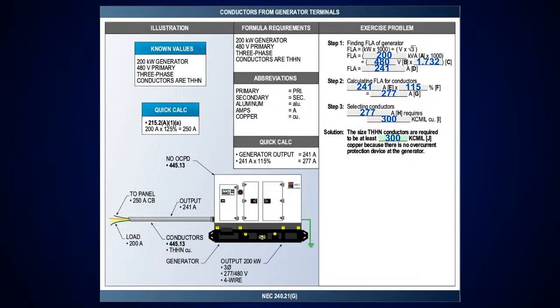Here's another one where I'm doing the conductors from the generator terminals. Okay? I've got a 241 amp output. We're telling you that's what it is. How do I know that? Well, I've got a 200 kVA generator here, and I've got 480 volts. It's 3-phase, 1.732. Okay, and it'll give me 831 volts. Divide all that in, that gives me 241 amps.